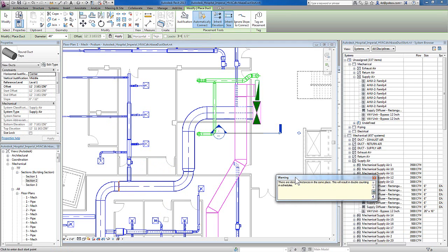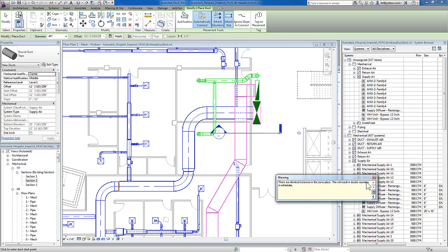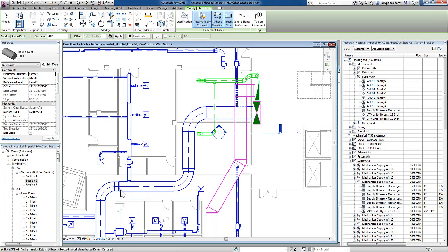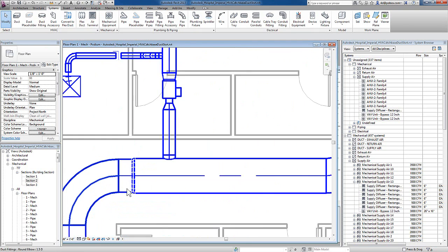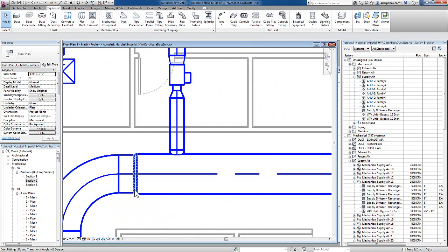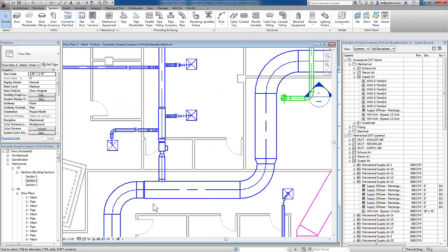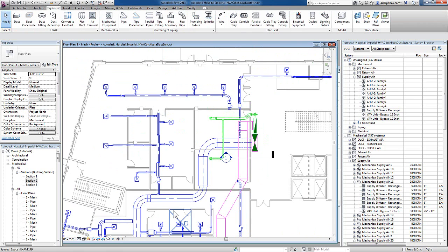Here I see that Revit has given me a warning. These types of warnings, which are a little yellow, are ignorable warnings, meaning that if you do anything else, they will disappear. You can get the list of warnings later, but what I'd like to do is take care of these as they happen. So, here Revit has placed a fitting on top of another transition or a transition on top of another transition. I will just manually go delete that transition so I don't have to correct that later. So always a good idea to take care of these as they happen.